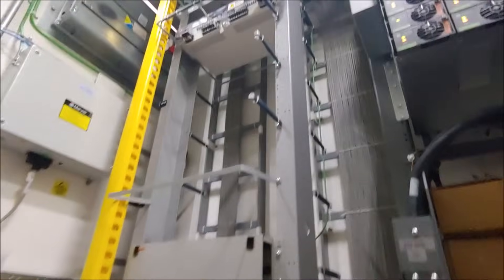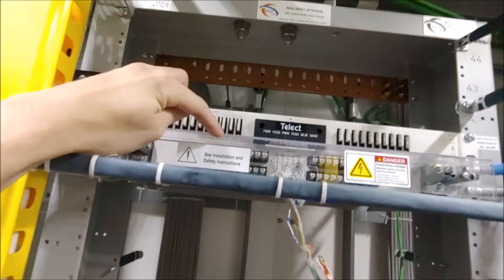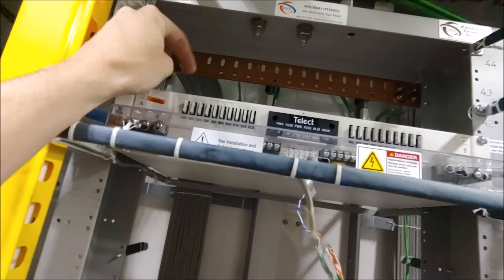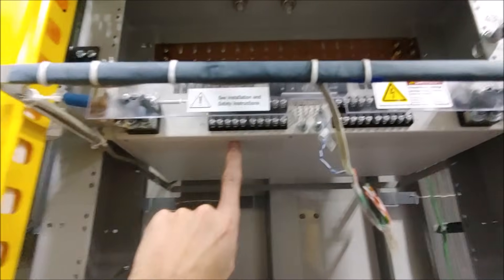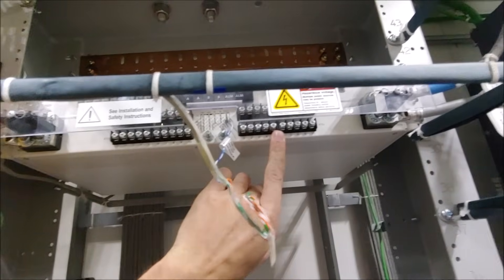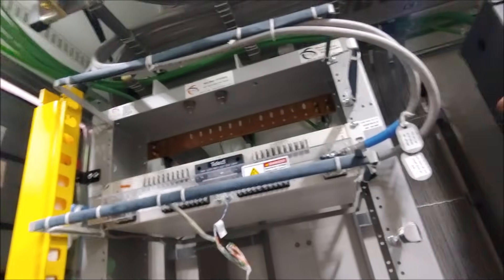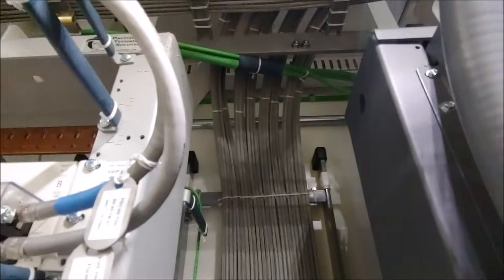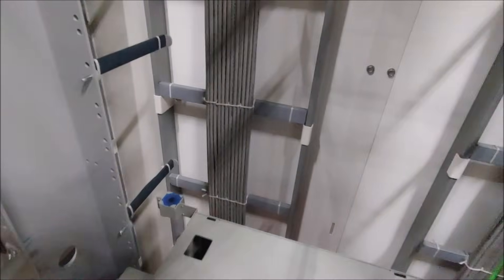There are the breakers for the battery disconnect. This is an empty FIF rack for future equipment, with the exception of the top where we have a power distribution unit. We have 48-volt reverse polarity going into the PDU, and these little slots are where your fuses would be located to power all your other devices. The cable lacing in here is absolutely beautiful — I'm a big cable organization freak and whoever did this did an awesome job.